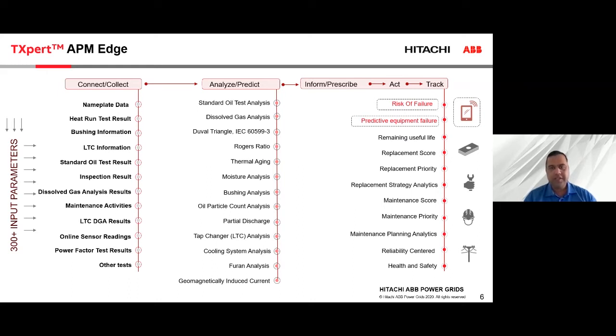And once we have the data, we do a lot of analysis. We use standard oil test analysis and DGA analysis. If you have the CTs and the top oil temperature, we can calculate the thermal aging of the paper. Depending on the bushing information, we do bushing analysis. We can do particle count, PD, tap changer analysis, cooling system, and Furan. Then we use all of these algorithms to calculate the risk of failure of the transformer. And depending on the data and the analysis, we calculate the remaining useful life of the transformer.